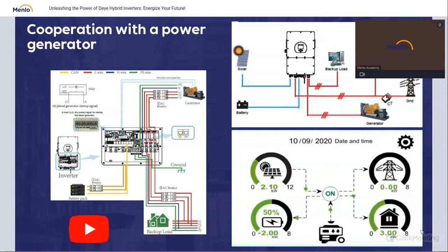Okay, second way how you can use gen input. I mentioned the AC couple retrofit AC charger. It's a good solution because it allows you to expand an existing installation, not replace it with a new one. It has only one problem: if the grid is off, your on-grid inverter is turned off, and you have only backup in the batteries, and the battery will not charge in any circumstances as long as the grid doesn't turn back.